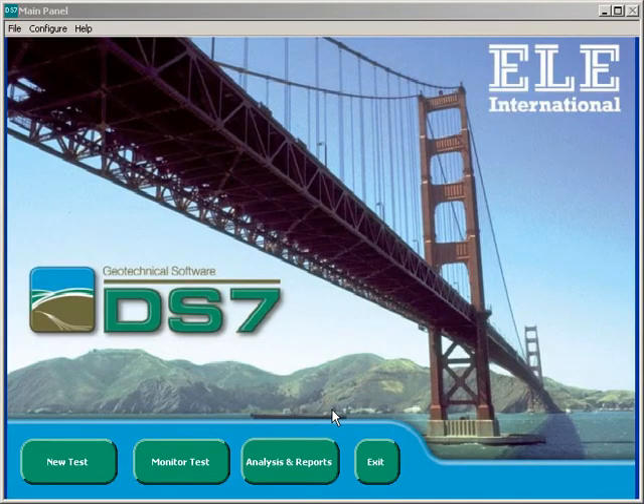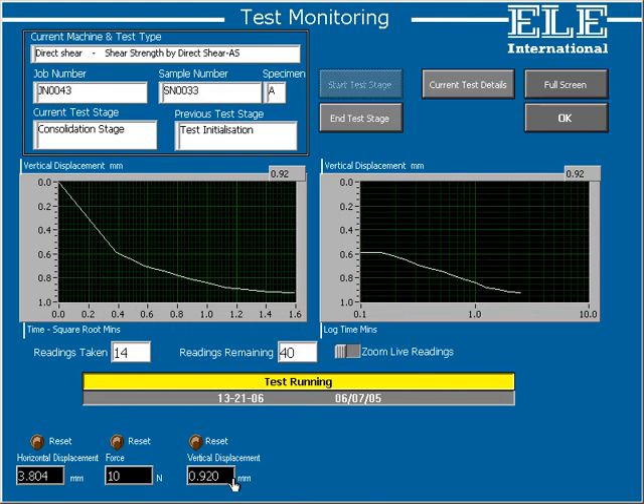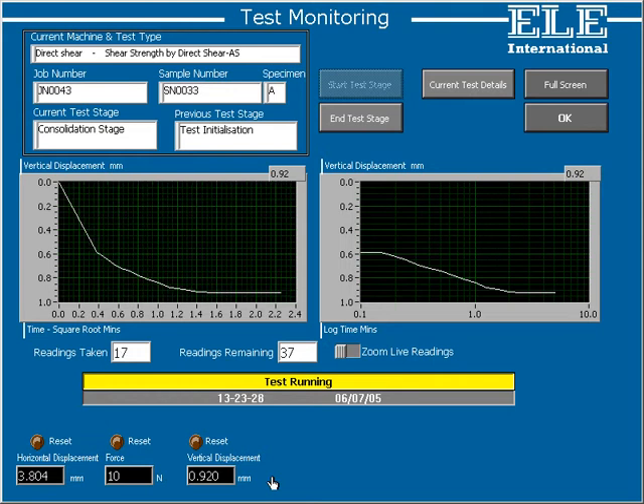Just to show that DS7 is truly multitasking, let's look at another test which was previously set up and is now running. There's a direct shear test being run to ASTM standards and its status is running. The current test stage is a consolidation stage, with the previous stage being initialization, so this test is just starting. Because this is a direct shear test, there are three transducers showing on the lower part of the screen instead of the one transducer for the oedometer. DS7 is intelligent — it knows which transducers and parameters to display for the particular test being viewed, and displays them using the correct units of measurement.